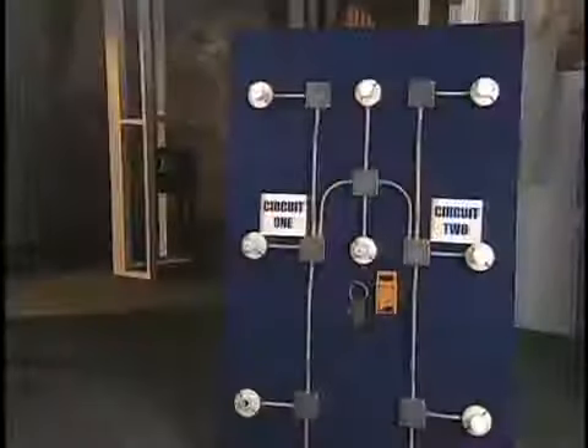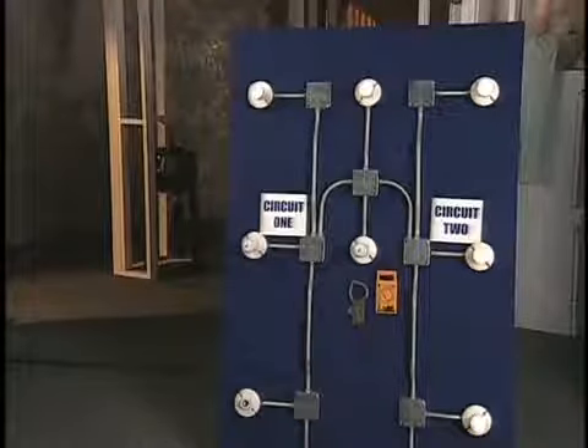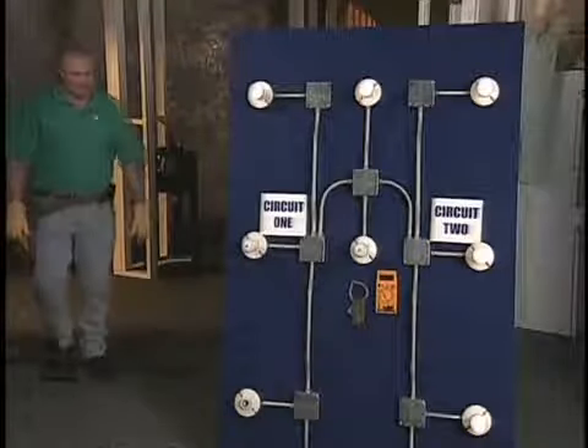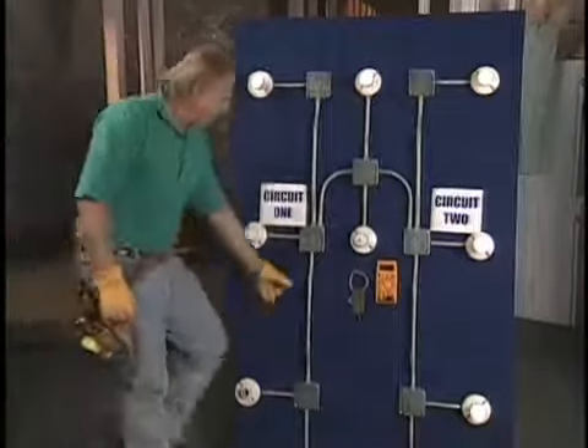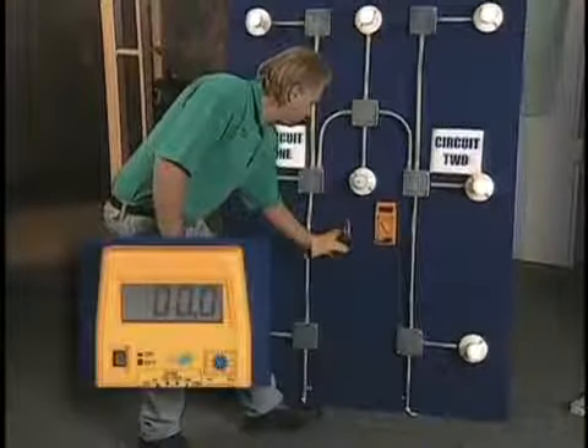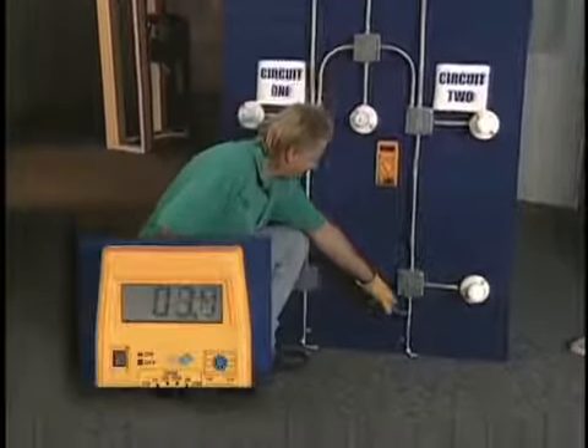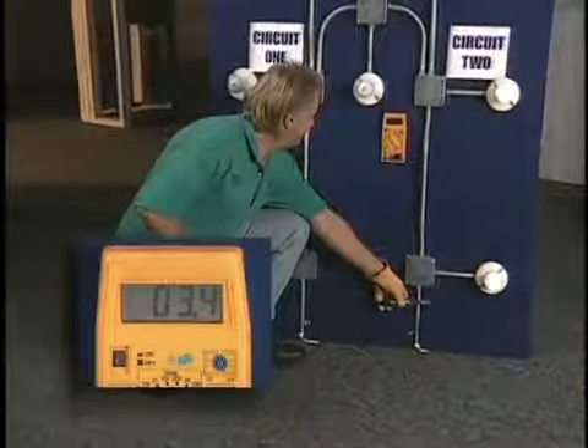Your next step is to trace the net current circuits to the location of the error. If you have an idea where the error may be found based on your panel investigation, go to it. If not, follow this procedure. You will usually be working in the ceiling. To show the tracing technique, we will use this live model. Using your clamp-on, follow the conduit with the net current to the first junction box.